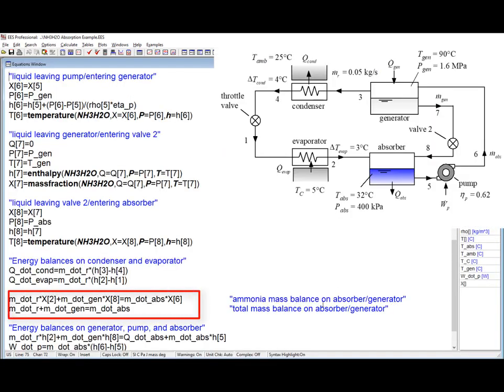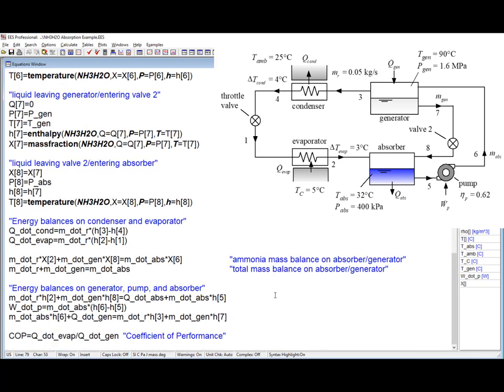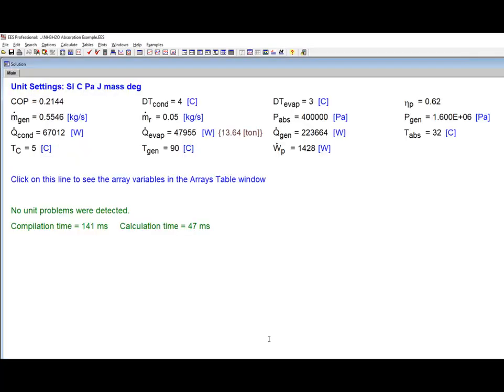An ammonia mass balance on the absorber and a total mass balance on the absorber together will allow you to solve for the mass flow rates that must be pulled from the absorber and also pulled from the generator. And then finally energy balances on the absorber, pump, and the generator allow us to calculate the remaining energy flows. So the coefficient of performance or COP of this cycle defined in terms of the refrigeration effect divided by the thermal input to the generator can be computed. And the COP under these conditions is only about 0.21. So there is various modifications to the cycle that can be implemented in order to improve this value somewhat.